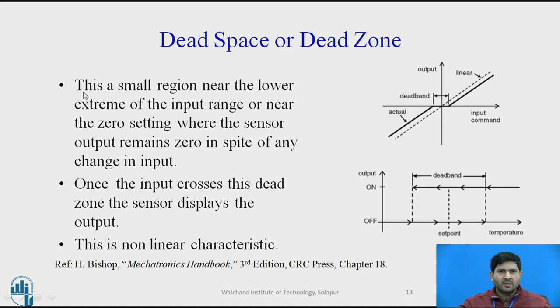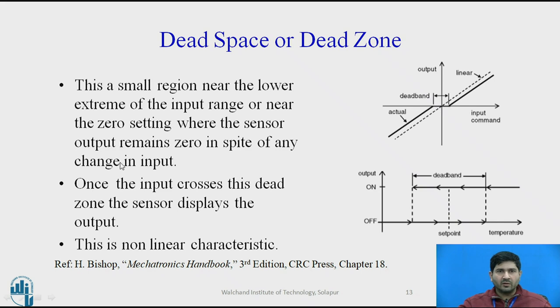Another characteristic is dead space or dead zone — a small region near the lower extreme of the input range, or often near the zero setting, where there is no change in output despite any change in input. This can sometimes be a desired feature if you do not want any spurious output; once the input crosses this dead zone, the sensor can display its output. This is also a non-linear characteristic.